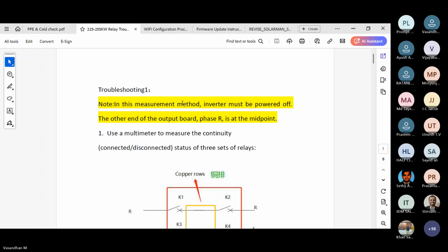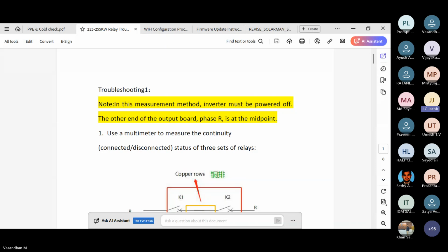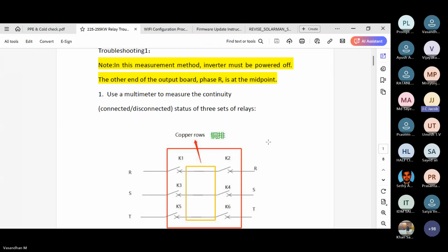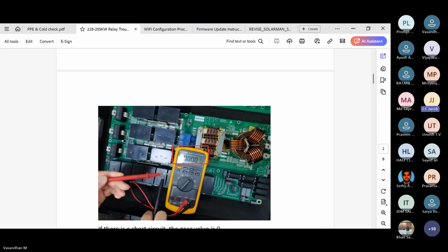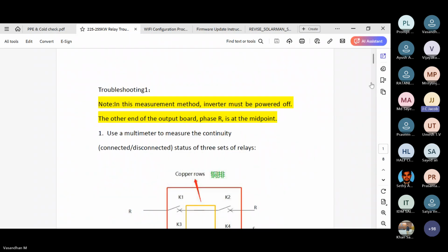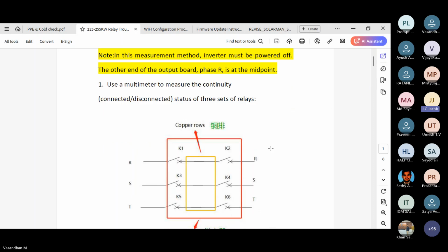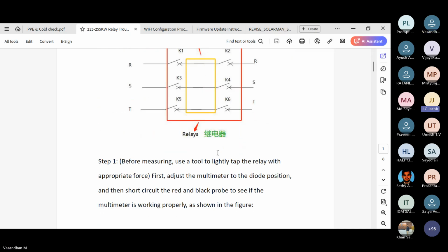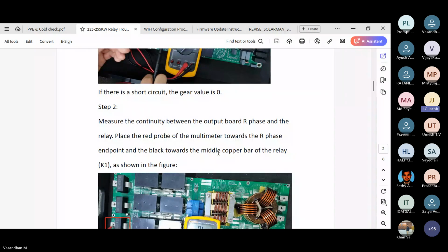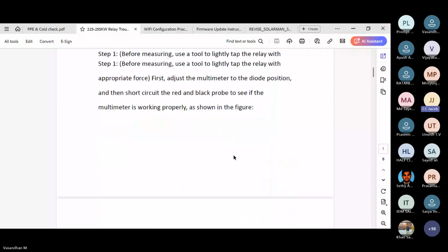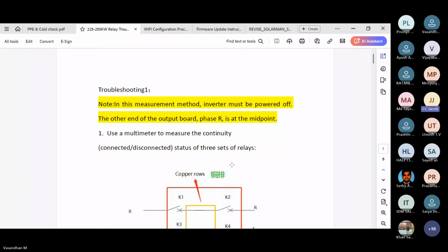Sir, he is asking what is the default range of the grid supply. 110 is the lowest voltage, 295 is the highest voltage, but the inverter will produce the voltage depending upon the DISCOM voltage where you are connecting at your local DISCOM. If local DISCOM is 245, the inverter will produce 245. If local DISCOM is 220, the inverter will produce 225. Like that, 5 to 10 volts more than the grid voltage. So there is no question of a default band. Undervoltage setting can be set up to 110 or 150 if required. Similarly on the higher side it's 295, but it is better to always keep it at 270 so that the customer doesn't get a high voltage of more than 270, which is dangerous for his house.